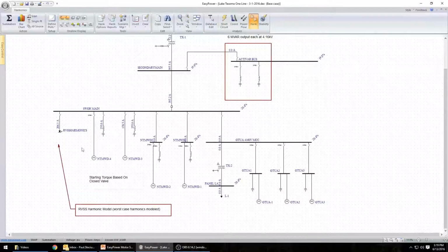For instance, I might have this motor running and be starting this motor. Typically the way soft starts are operated is the soft start is turned on, and then at a later point in time, once the motor is operational or at full speed, the capacitor is switched on. So the starting sequence would be motor starting through the soft start, and then the power factor correction capacitor being installed or being turned on once the motor is up and running.